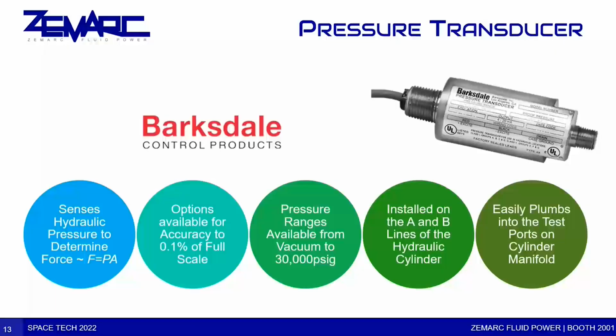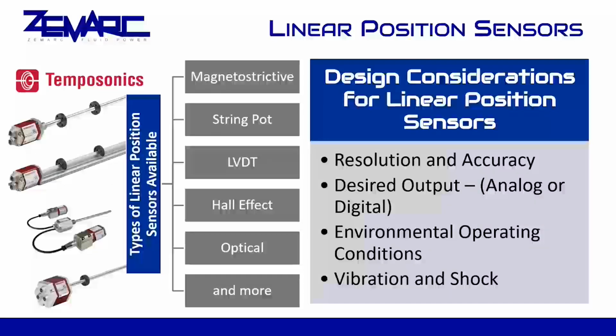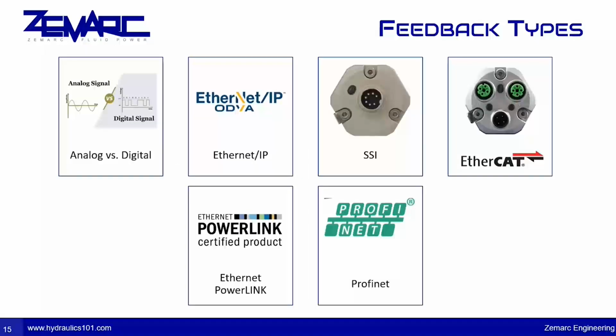So the Barksdale pressure transducer, which as we stated before, takes an analog reading of a pressure and converts it into a digital reading for your computer like a PLC. And on to linear position sensors. And here are some numerous options that we offer through Temposonics, but just a little bit further on the discussion of linear position sensors. What these do is they take an accurate reading of the cylinder as it actuates. Some considerations that must be made for these types of sensors are resolution, accuracy, desired output, operating conditions, and vibration and shock. So, with these sensors, there's a multitude of feedbacks. But with stuff like the Temposonics, you can get digital feedback or analog feedback, and it really depends on the specific sensor and application.